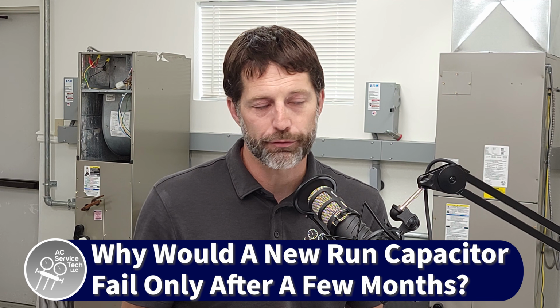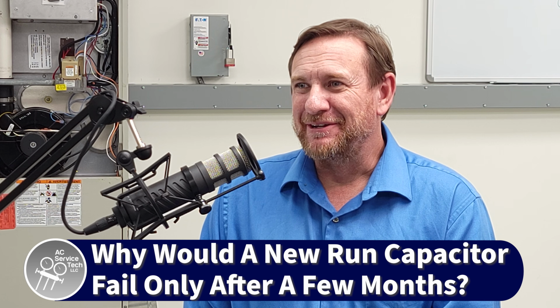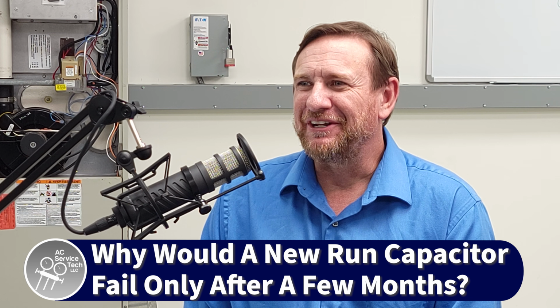We have a technician by the name of Matt asking, why would a run capacitor blow twice in a matter of just a few months? Well, my opinion is it probably was a lower quality run capacitor. Or maybe it was a good brand, and every manufacturer, everything made, has failures. But that was definitely a bad capacitor. So that's an internal failure, in my opinion. Yeah. So you don't think that could have something to do with overheating over a period of time? But it's probably, I think you're right.